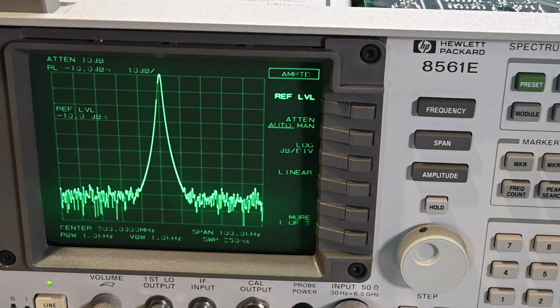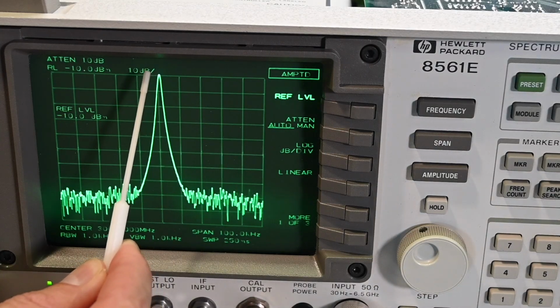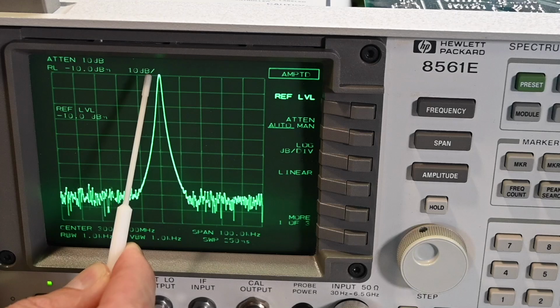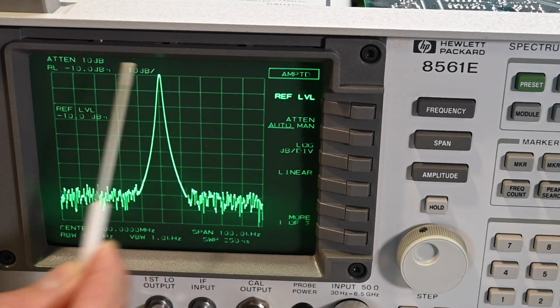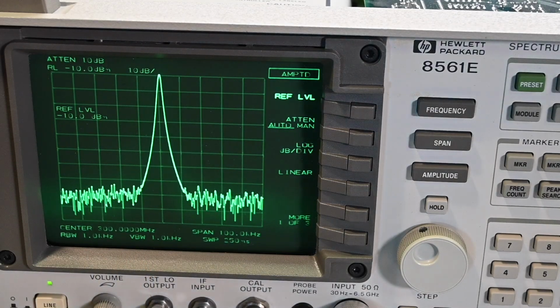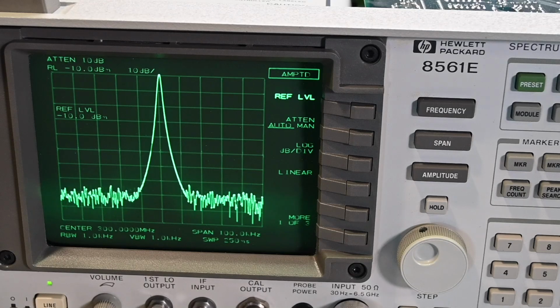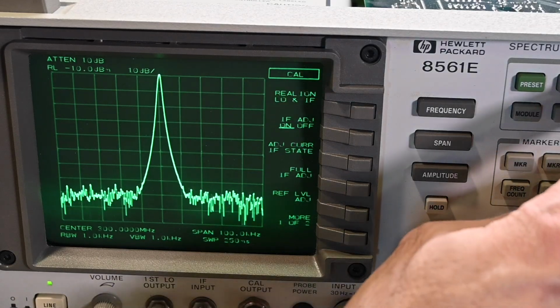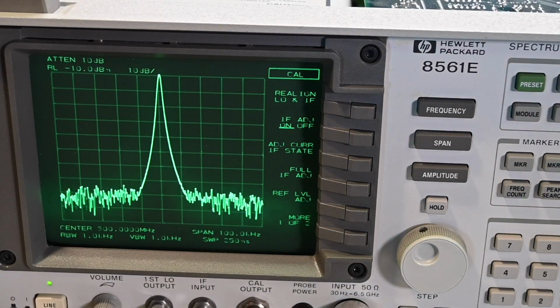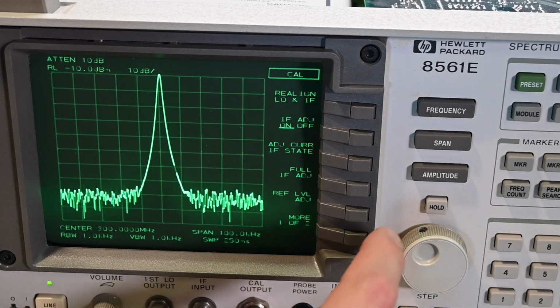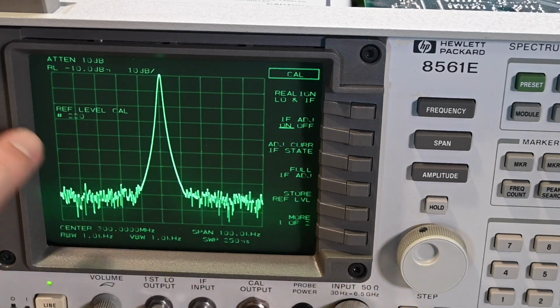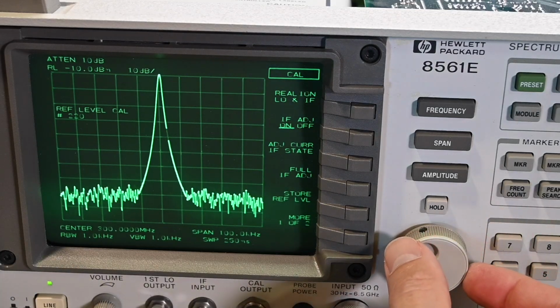So this peak right here, we actually want that peak just to touch that top reference line, and to my eye it looks like it's just a little bit over, so that needs to touch. And again, we know we have a very accurate minus 10 dBm signal going into the spectrum analyzer. So over on the calibration menu, just hit the cal button, and right here it looks like reference level adjust.